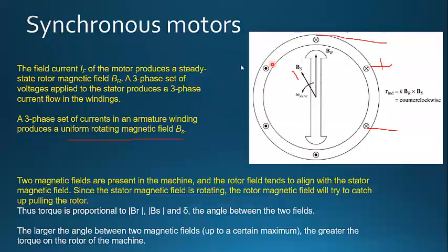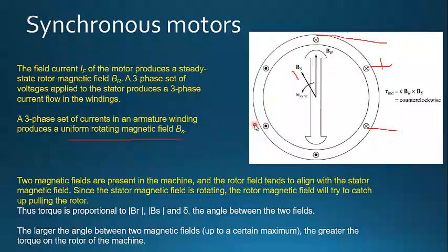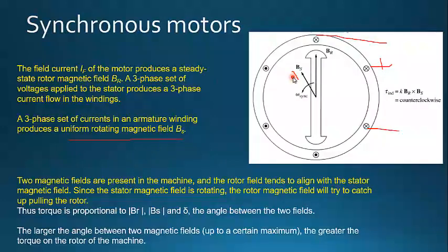A field current If in the motor produces a steady-state rotor magnetic field BR. So if you excite the field windings, you get a magnetic field created on the rotor, which we call BR. Now if you excite the armature windings with a three-phase AC power supply, we create a uniform rotating magnetic field called BS. So we now have two different magnetic fields in the motor: BR, which is a stationary magnetic field on the rotor, and BS, which is a rotating magnetic field on the stator.